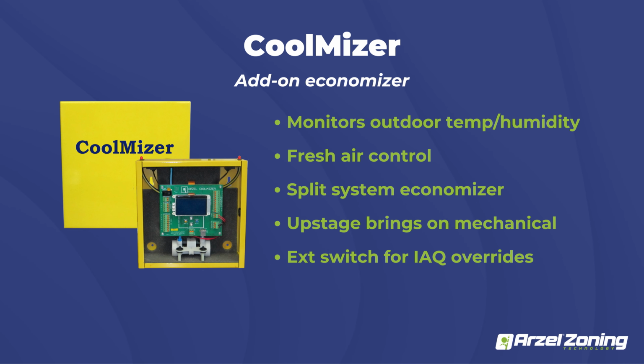Last panel that we offer that's not zoning related, this is going to be our CoolMizer panel. What this panel actually does is it gives you an economizer function on a residential piece of equipment. So you would run an outdoor duct going outside to draw in that cool air on the shoulder season, so your early spring, early fall. Instead of the customer having to open windows and have all those allergies come into their house, they're able to actually bring that cool air from outside, still filter it through their HVAC equipment, and then deliver that air to the space to cool it rather than running the mechanical cooling.